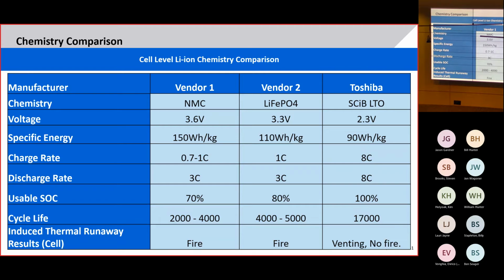The compromise for LTO is energy density. The energy density of the power pack is nominally less than for the other two chemistries, NMC and iron phosphate. You can see here voltage is 3.6, 3.3, and specific energy is 150, 110, and we're at 90 watt-hours per kilogram. That's nominally. Once you actually install and use the batteries, that specific energy density delta becomes less, because you can only use 80% of this 3.3.